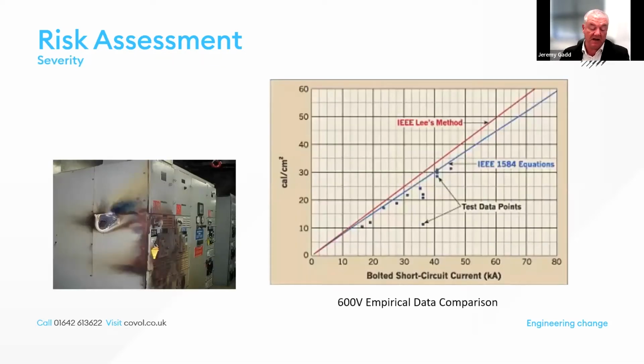Looking at the severity, this chart shows the relationship between incident energy and fault current. And this is using 600 volts empirical data. As you can see, the relationship is approximately linear. And the IEEE 1584 standard, which we'll come on to later, uses this relationship in arc flash calculations. But note that this calculation is only used up to 15 kV. Anything above that uses Lee's method. Ralph Lee produced a set of empirical data, and over 15 kV, 15,000 volts, that's the point where you start to use this Lee data.